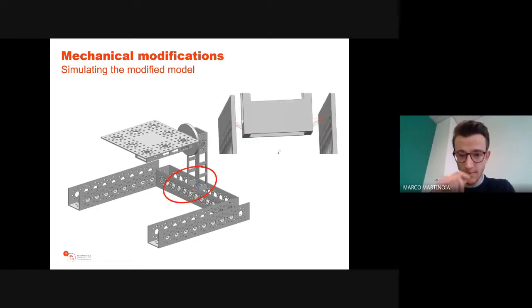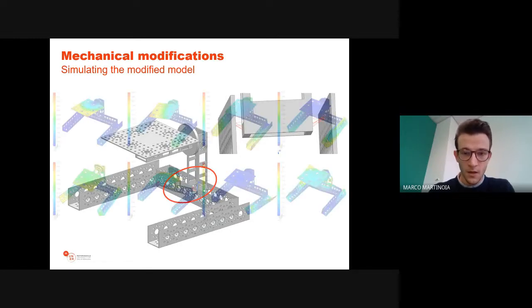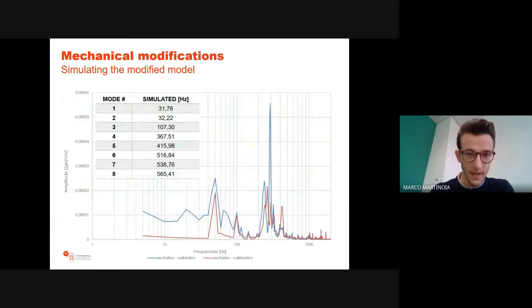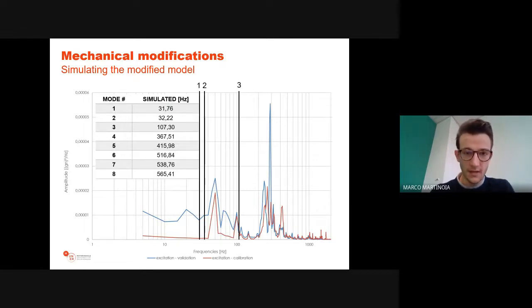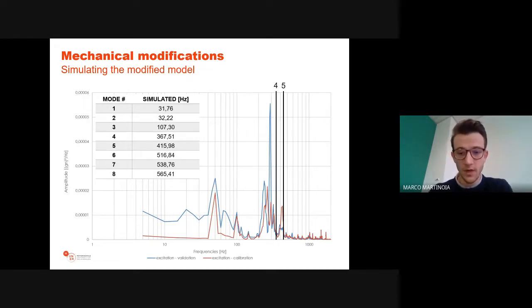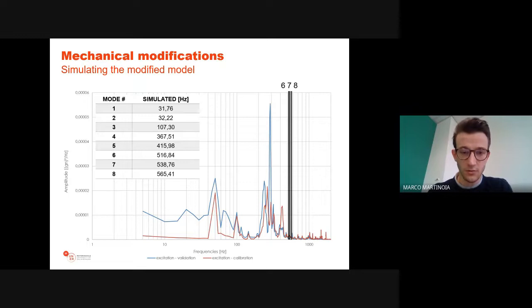Thus, the only mechanical connection which we didn't model before was the one between the vertical arm and the base, which was modeled with some RBE2 in order to resemble the very stiff connection between the two parts. The results obtained are these. Comparing the natural frequencies obtained with the excitation profiles, we can say that the first 3 modes are not cause of concern. I want to remind you that the first 2 peaks at 50 and 100 Hertz are the ones coming from the noise of the power grid, and the 4th and 5th modes overlap the high peak of the excitations, while the last 3 natural frequencies are not as much cause of concern as the 4th and 5th modes, but have to be taken into account.